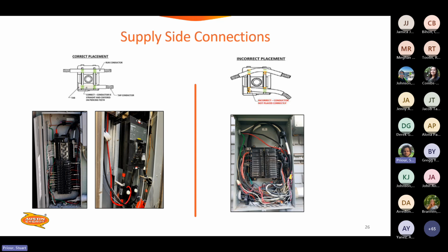So how to do a supply side connection properly. On the left there, you can see that the conductors that are tapped, the main conductors, are tapped in a straight run of conductor. And in the photographs from the field there, you can see that there's nice ample room for those taps, and they've tapped them on a straight run of that conductor, not in a spot where it is bent and not properly attached.